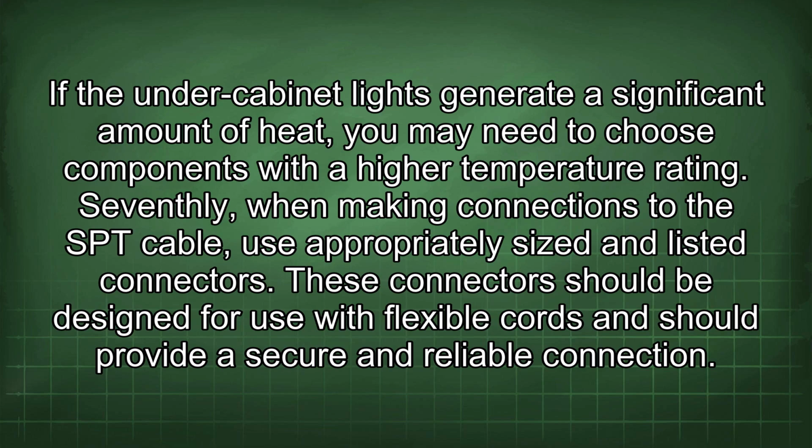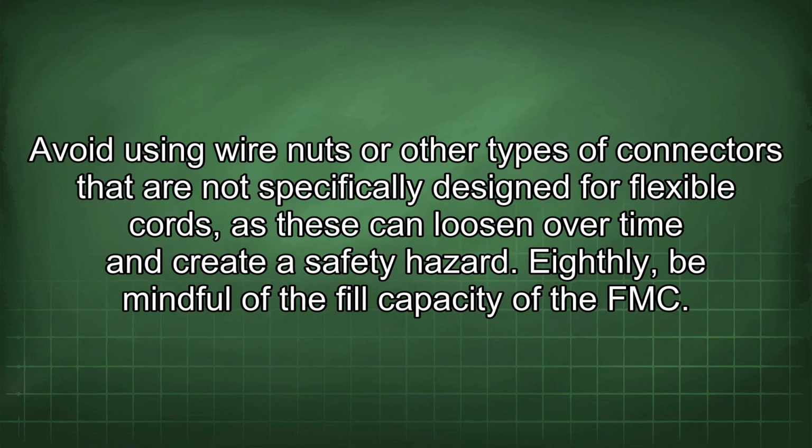rating. Seventhly, when making connections to the SPT cable, use appropriately sized and listed connectors. These connectors should be designed for use with flexible cords and should provide a secure and reliable connection. Avoid using wire nuts or other types of connectors that are not specifically designed for flexible cords, as these can loosen over time and create a safety hazard.